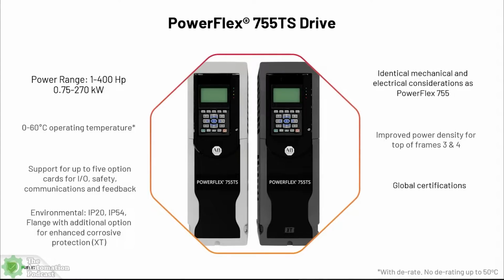It has a 0 to 60 degrees C operating temperature, extended from our 755 drives. We'll talk a lot about the enhancements in performance between the 755 and the new 755 TS platform—temperature being one of the big winners here. Before, we were able to operate at 0 to 50 degrees C with the PowerFlex 755; now we've enhanced that up to 60 degrees C with the 755 TS control. There is some derate from a power perspective to hit that 60 degrees C operating temperature, but it provides a little more flexibility, especially for folks working in high ambient temperature conditions.